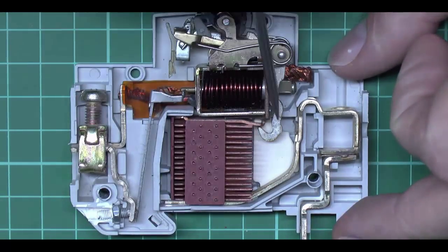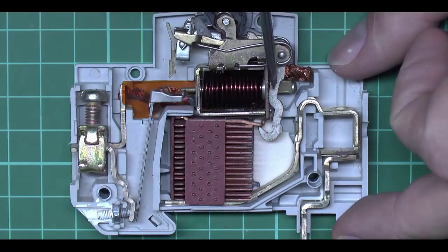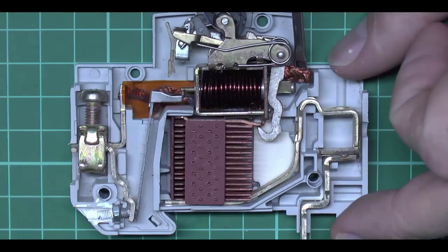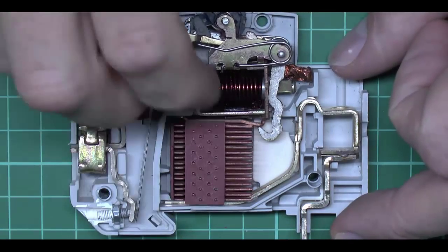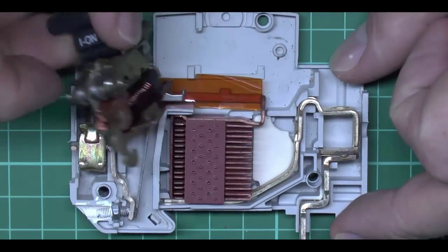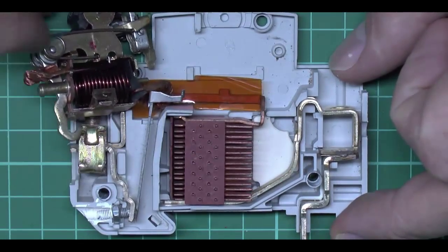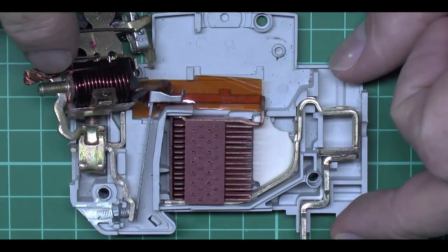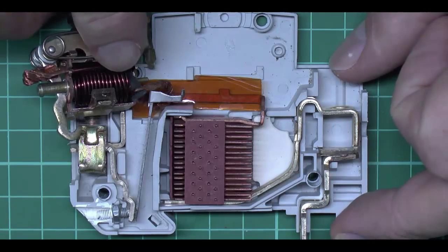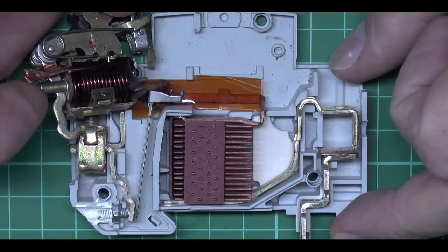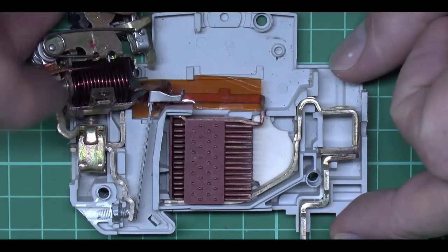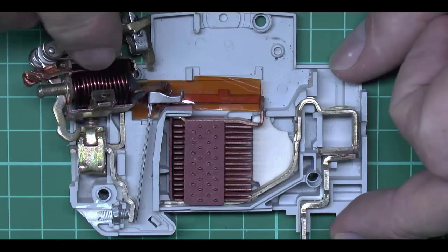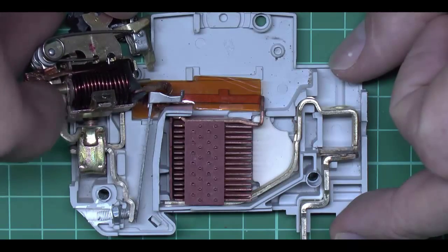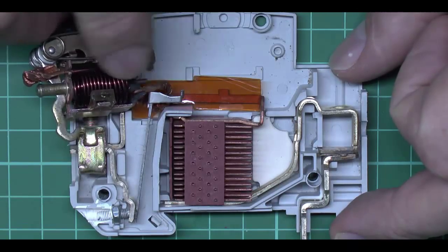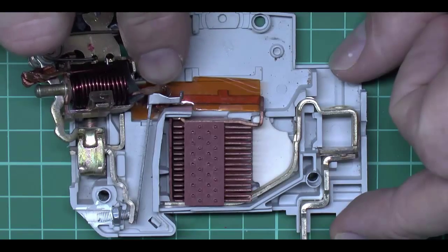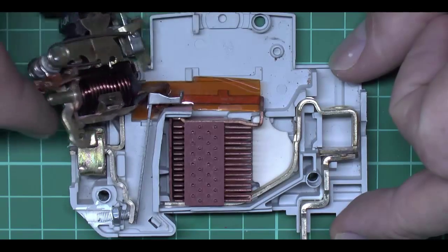So assuming it's in the closed position, we'll come across to the hooked piece there, and it's actually connected to this piece of braid on the back there, which is not terribly easy to see, but that comes across onto the braid there, and then you've got a thinner wire there which forms part of this coil around this movable piece in the middle here. And this is basically a solenoid, so that when that's magnetised, this pin will move forward. And of course continues via all the wire there, and it comes out at the top here on another sort of braided connection piece there.